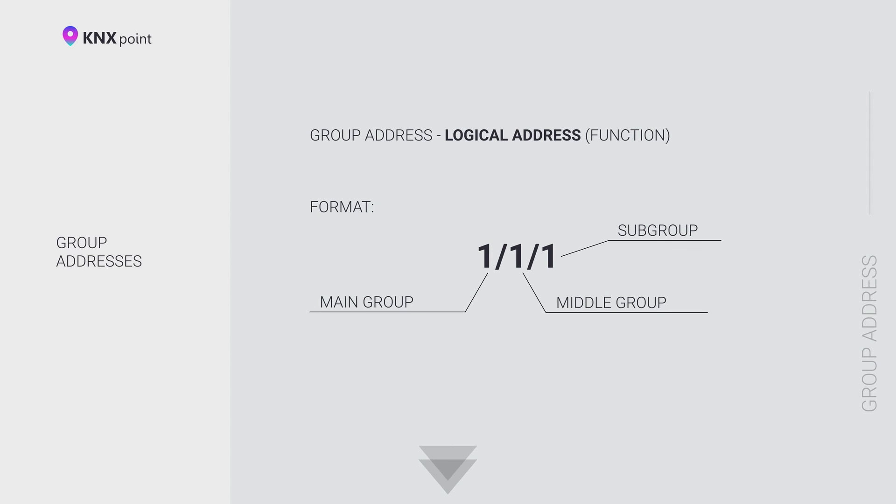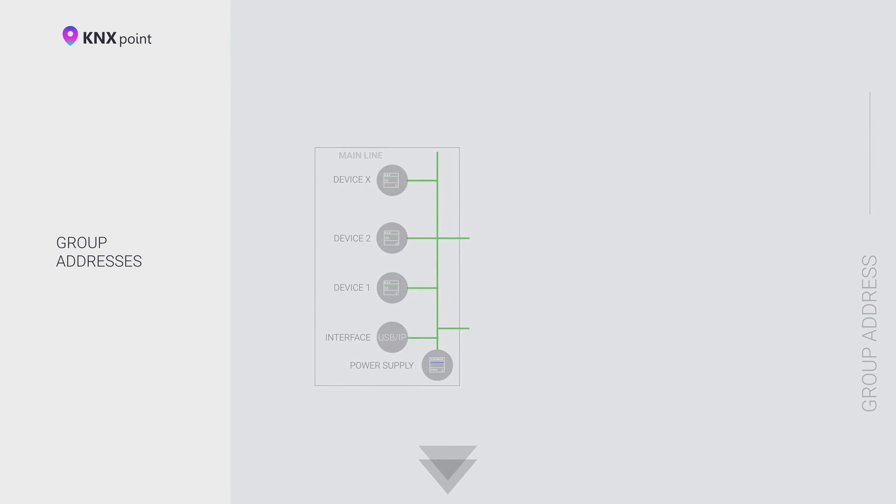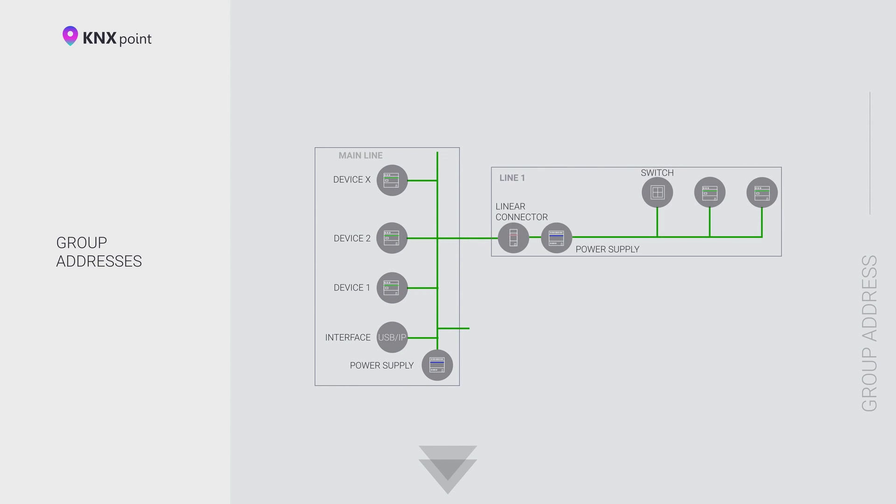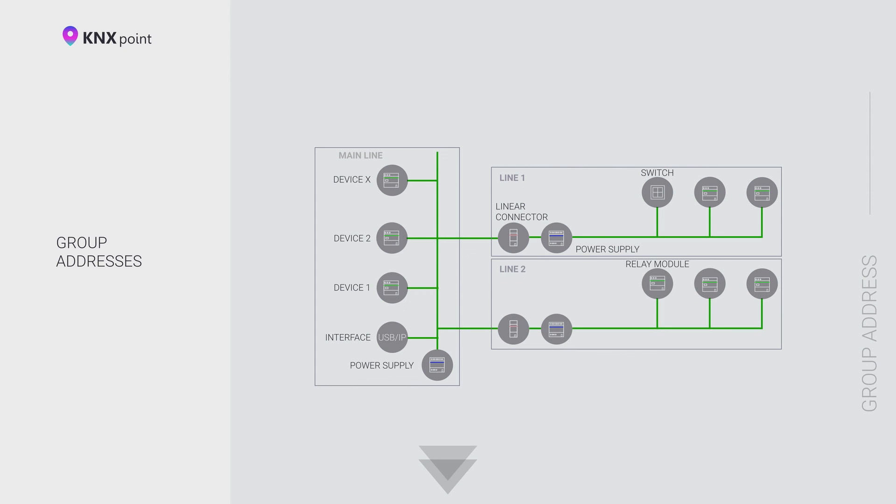The group addresses have the format of three numbers separated by a slash: main group, slash middle group, slash subgroup. This address structure affects the priority of command transmission to the bus. For the most important broadcast commands, we recommend using the addresses 0/0/0 and values close to it.